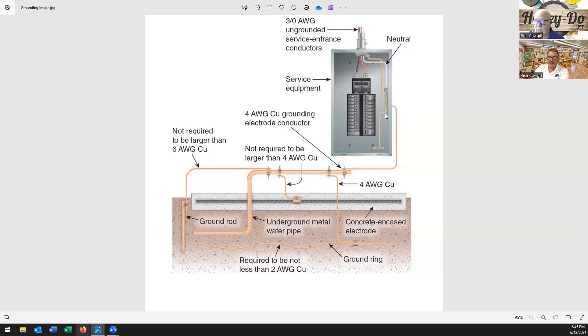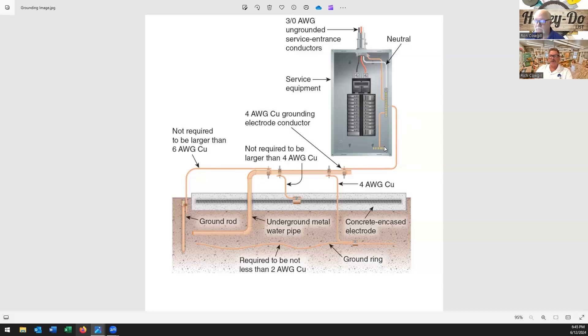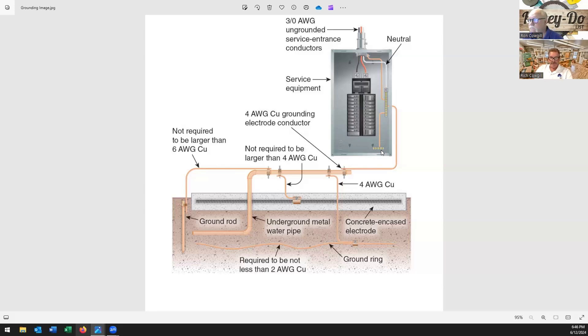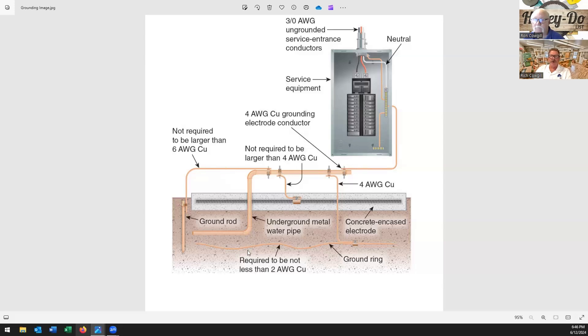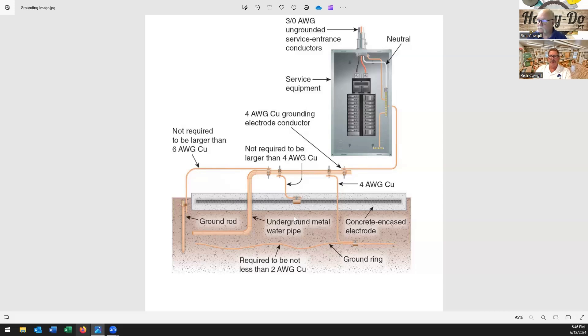Your neutral is always tied to that neutral bar. You've got your other bar - that one on the bottom of that service panel - would be actually something for you to put, you know, if you had other pieces of equipment whether it's a phone box, cable, whatever, those are where you're going to reattach those. I think most places like in the Chicago area you can actually ground, which it shows here, to your water pipe. For the most part you've got three quarter or one inch copper K run out for your water service, so that's your ground. They put a strap or a saddle clamp on that and that's your ground.